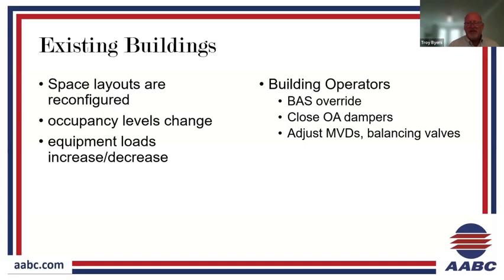But they have a tendency to maybe just go into the BAS, the building automation system, and override an airflow set point to respond to a hot or a cold call. Or maybe they're going to close their outside air dampers because they're not maintaining conditions. But this is just a symptom that needs to be addressed holistically, and not just make one change that's going to impact something else within the building system. They may have a tendency to adjust manual volume dampers. We've seen marks on ducts that say summer setting and winter setting for a manual volume damper, and somebody had that as their way of maintaining, but that building operator might have moved on. And again, I think it's a symptom of a larger problem that probably needs to be addressed. You might have some other good examples that you can drop in the Q&A that happen in existing buildings.